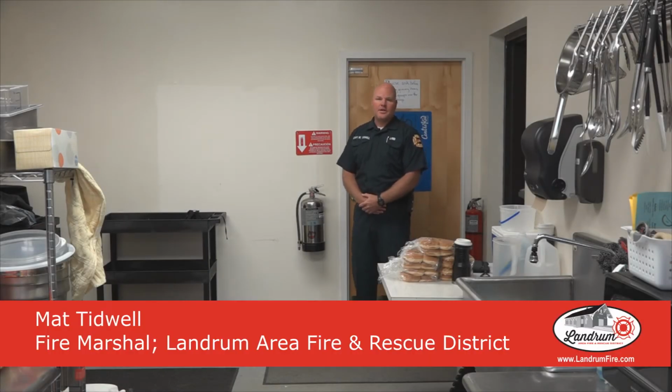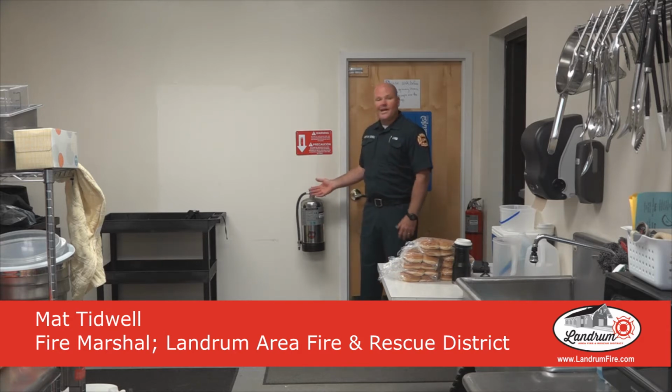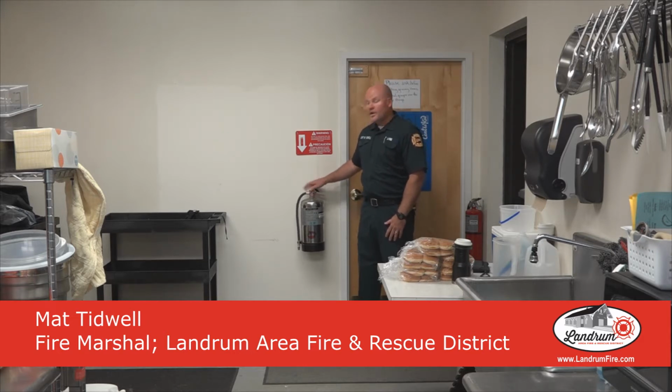All right, made it to the kitchen area. Kitchen area is big as far as cooking. Normally we have grease fires that can occur. I noticed that they have a K extinguisher properly mounted on the wall, fully charged. This one is specifically for grease fires. Water cans look just like this, a water extinguisher, and you can confuse them, but this one is properly labeled.